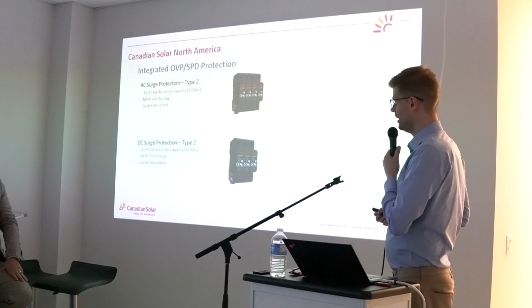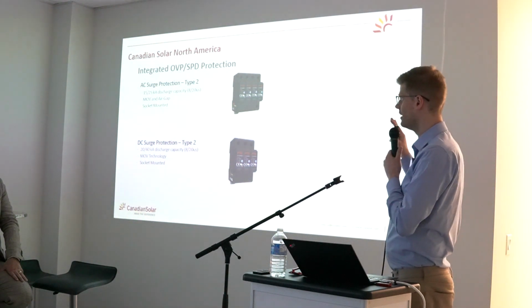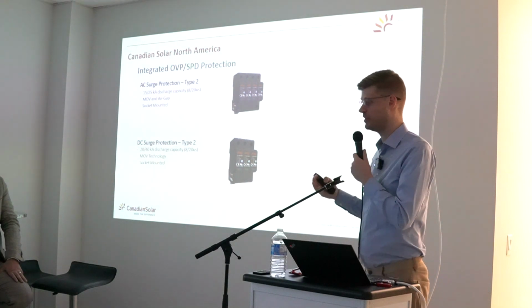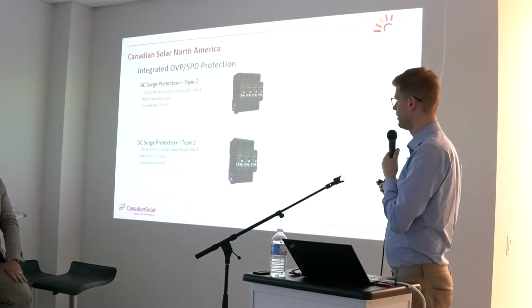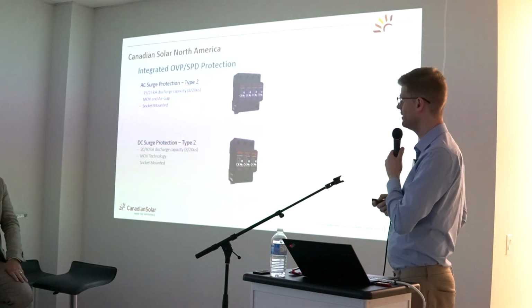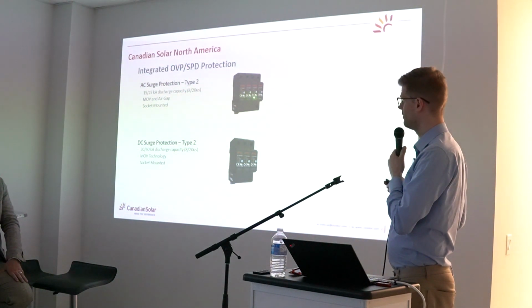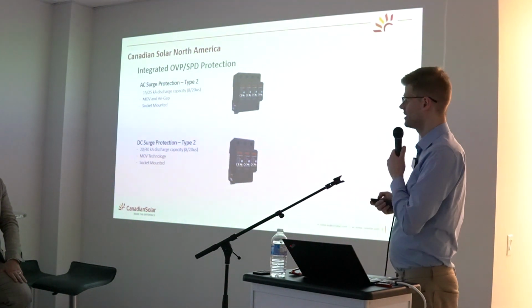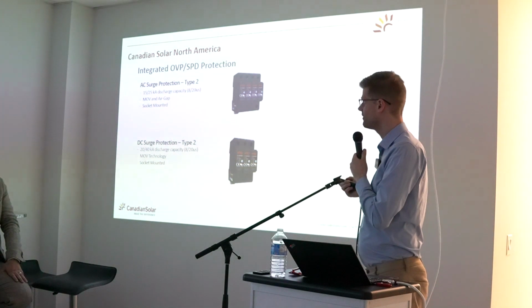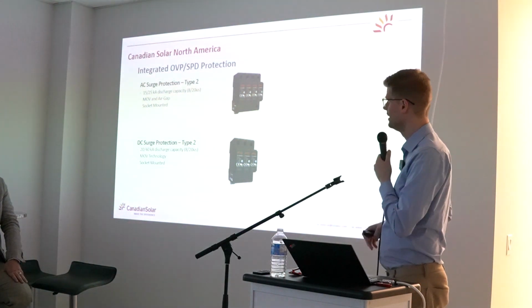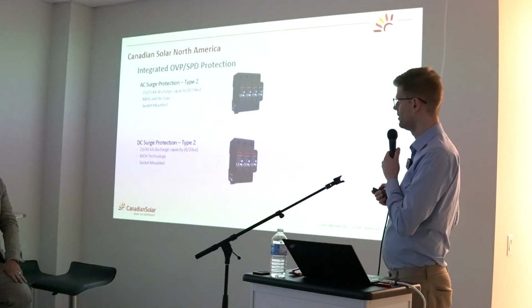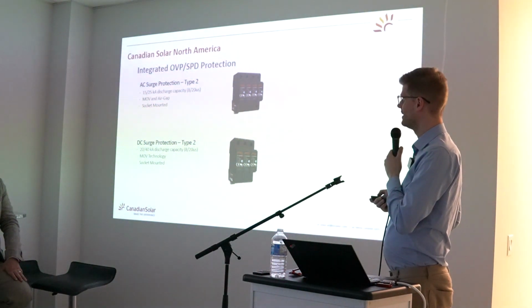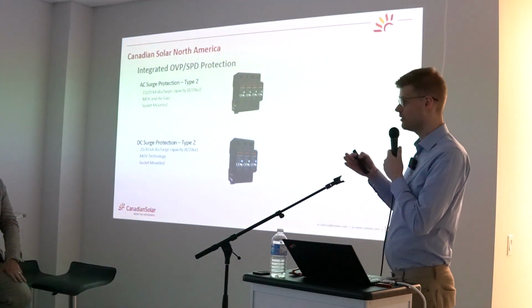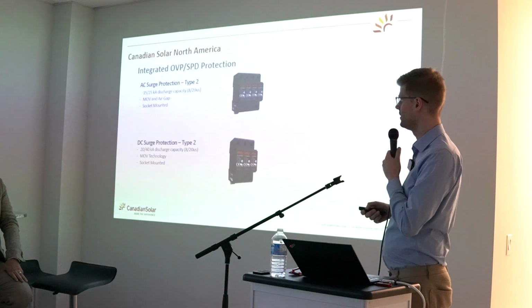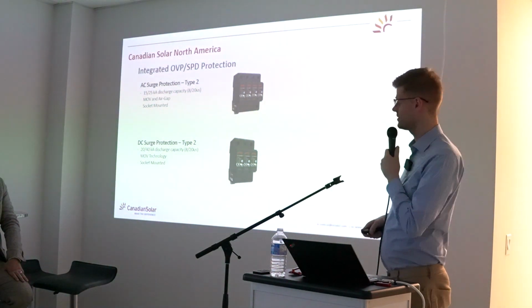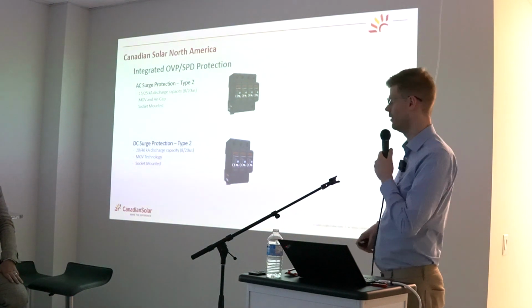The inverter also has, like some of the other ones in that scale, DC and AC surge protection, so overvoltage protection built in. And for Canadian Solar, they actually have socket-based AC overvoltage protectors. These are metal oxide varistors and one air gap arrestor. And the capability is actually quite sophisticated at 15 or 25 kiloamps rating on the output, so the AC side. That's a typical type 2 or type 1 for the air gap. And the DC surge for each of the inputs, so we actually have 12 of those built in, is also a metal oxide resistor and has also even higher, up to 40 kiloamps surge arrestor.